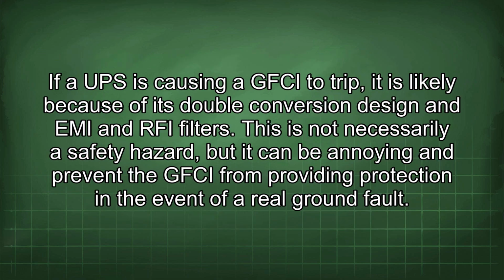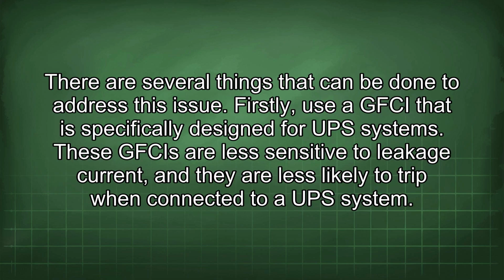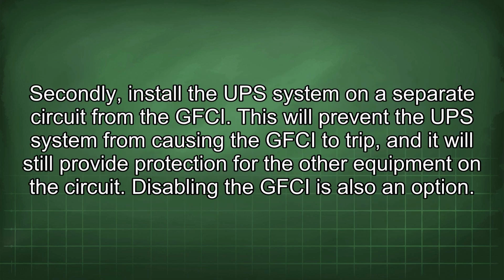If a UPS is causing a GFCI to trip, it is likely because of its double conversion design and EMI and RFI filters. This is not necessarily a safety hazard, but it can be annoying and prevent the GFCI from providing protection in the event of a real ground fault. There are several things that can be done to address this issue. Firstly, use a GFCI that is specifically designed for UPS systems. These GFCIs are less sensitive to leakage current, and they are less likely to trip when connected to a UPS system. Secondly, install the UPS system on a separate circuit from the GFCI. This will prevent the UPS system from causing the GFCI to trip, and it will still provide protection for the other equipment on the circuit.